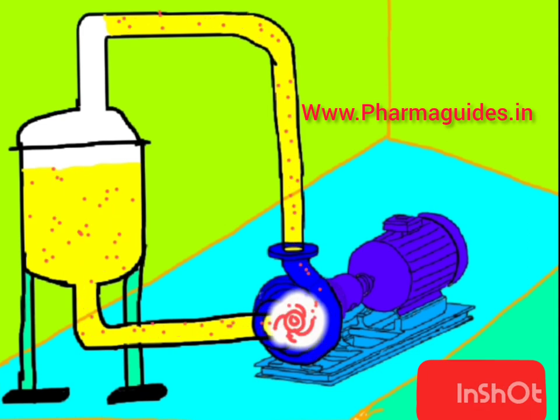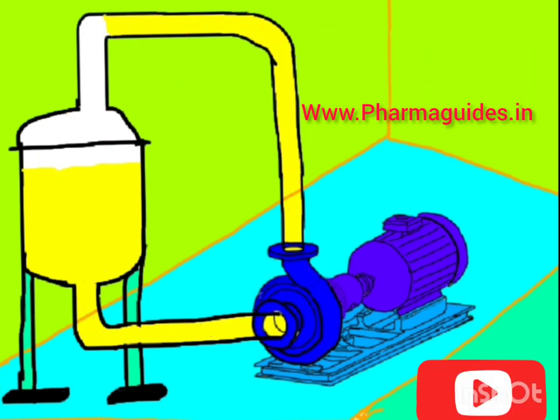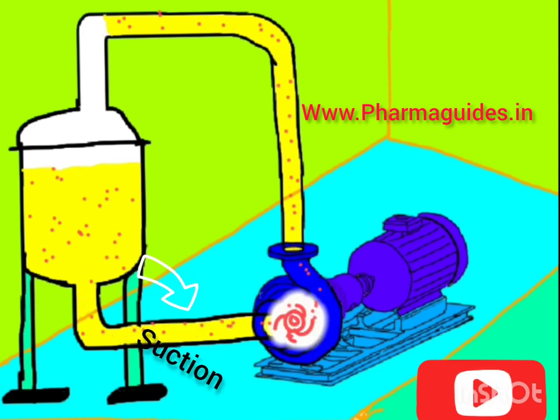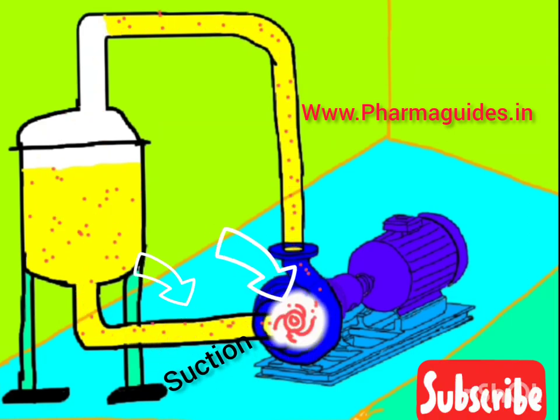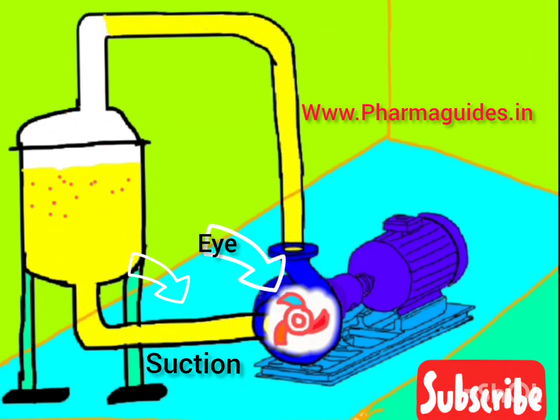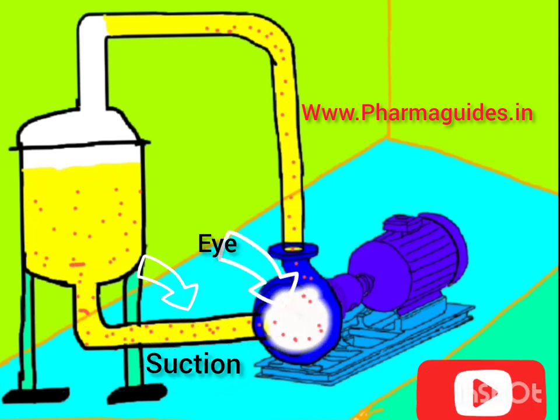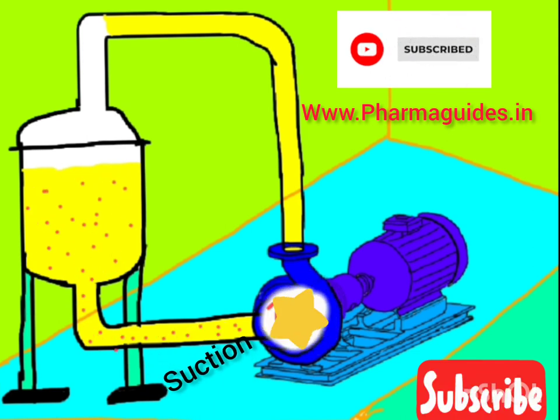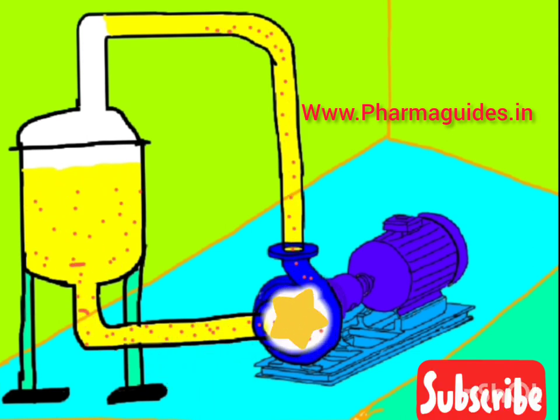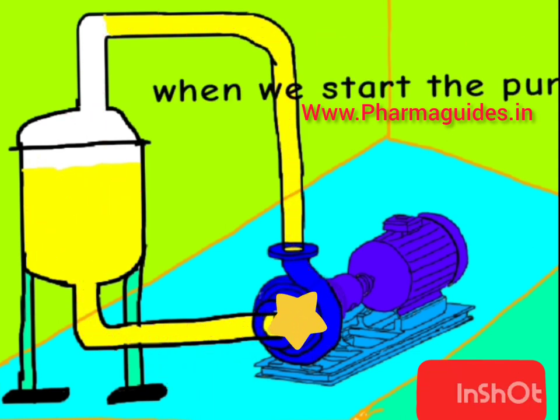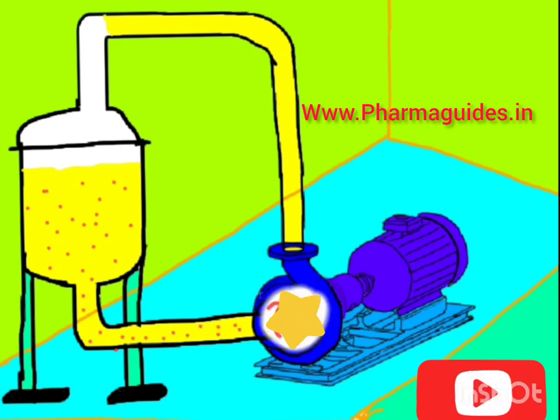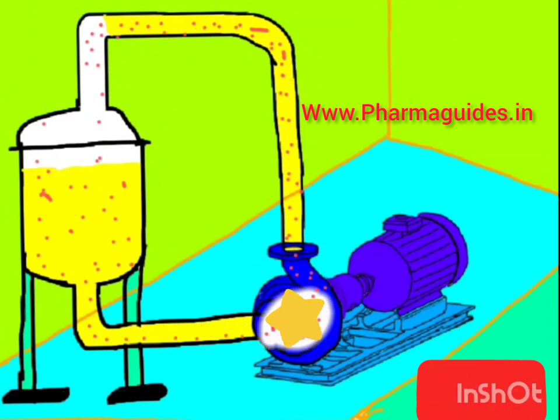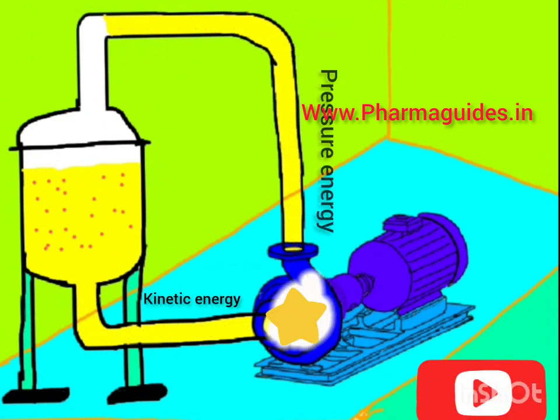The rotating impeller creates negative pressure or vacuum on the suction side of the pump, causing liquid to enter from the eye of the pump. The rotating impeller spins the water with it, creating centrifugal force inside the casing. In this way, kinetic energy is converted into pressure energy.